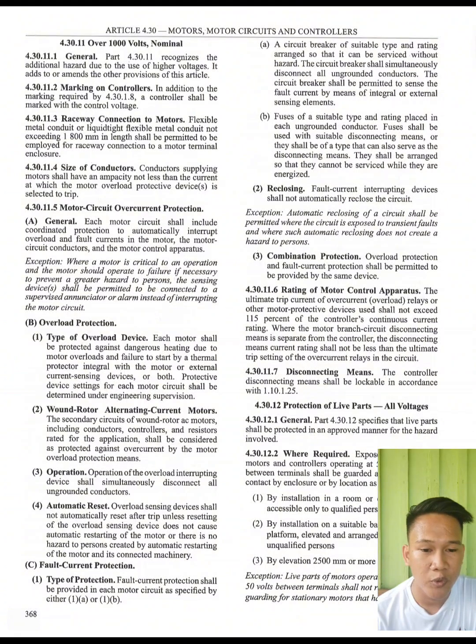Next is 4.30.12.2, where required. Exposed live parts of motors and controllers operating at 50 volts or more between terminals shall be guarded against accidental contact by enclosure or by location as follows. First, by installation in a room or enclosure that is accessible only to qualified persons. Second, by installation on a suitable balcony, gallery, or platform, elevated and arranged so as to exclude unqualified persons. Third, by elevation of 2500 mm or more above the floor. So, there is an exemption.